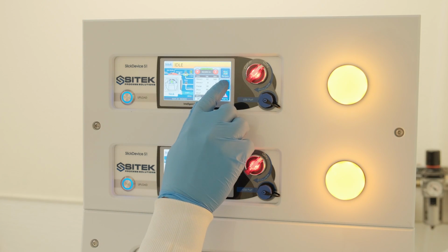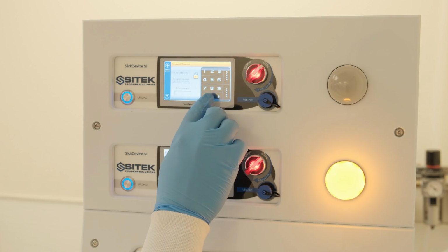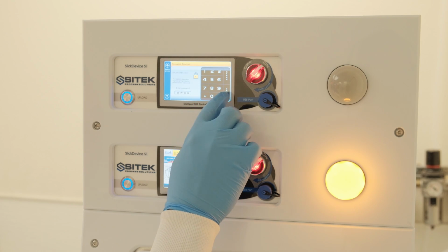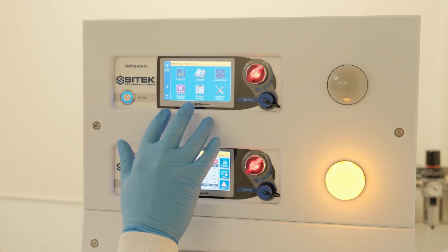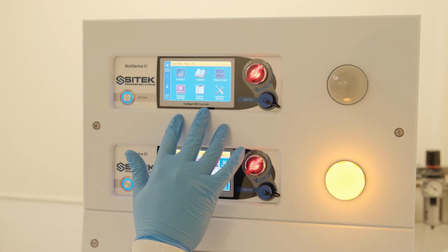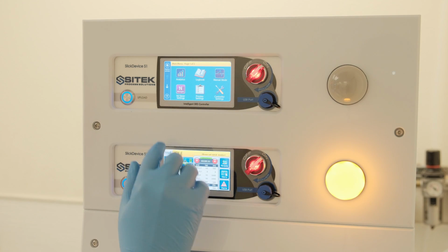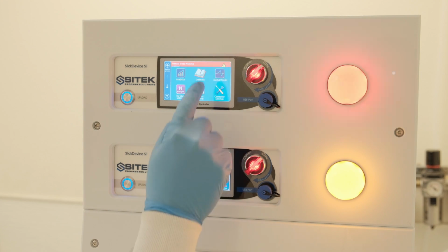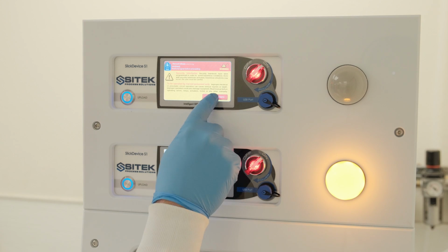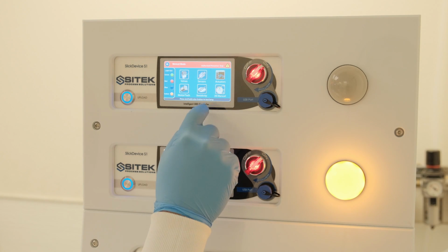Okay, so we have this chamber here which came up with an N2 heater alarm. When you are using a 101 controller, you're actually not going to get an alarm. You have to have somebody just notice that it was cold nitrogen blowing, which is one of the big drawbacks of that style system. On our system, we'd actually have that alarm that occurred. So we're going to come into manual mode and we're going to validate this problem.